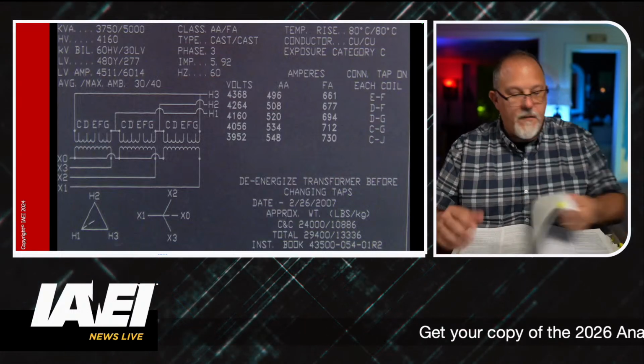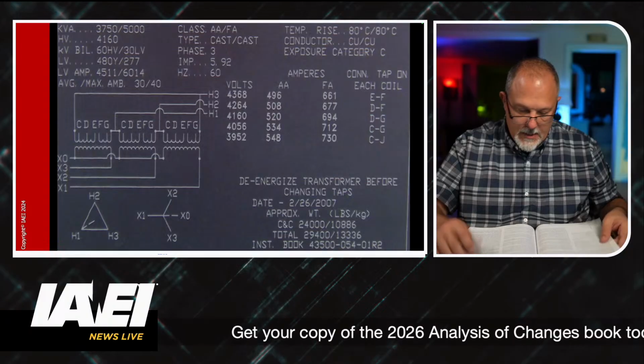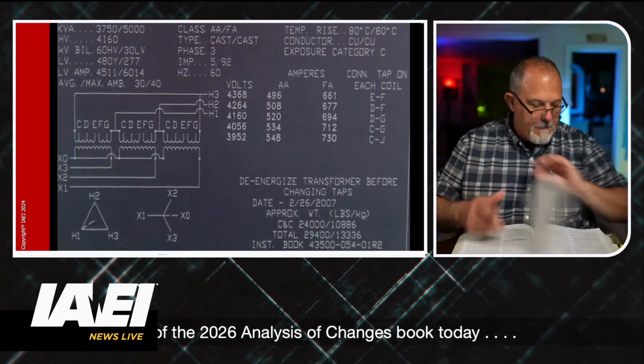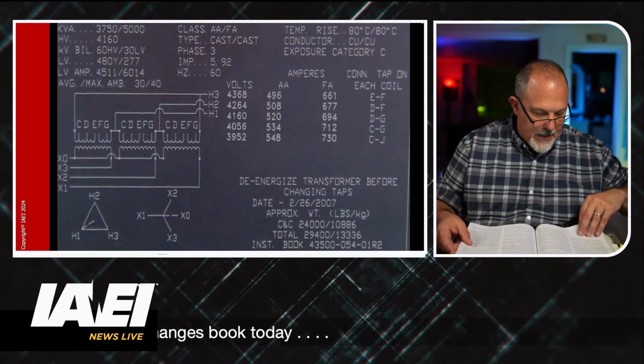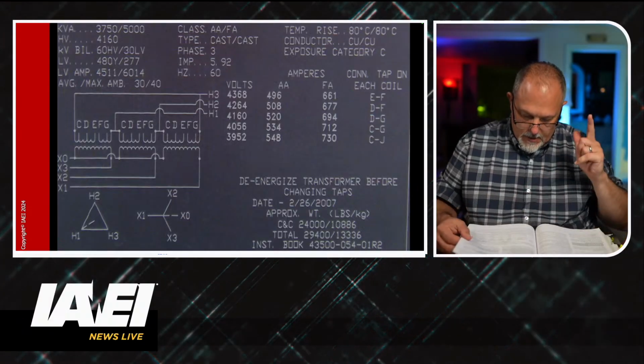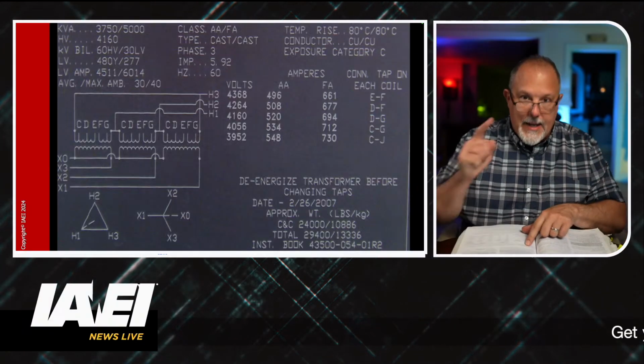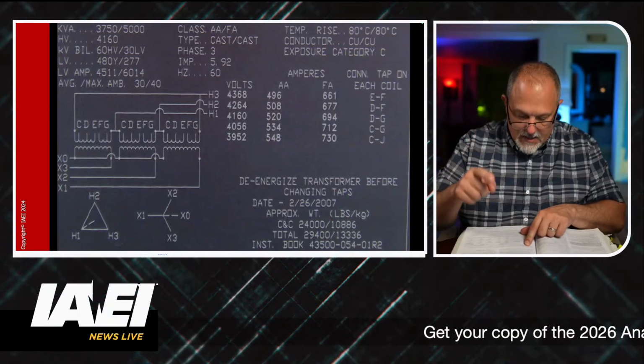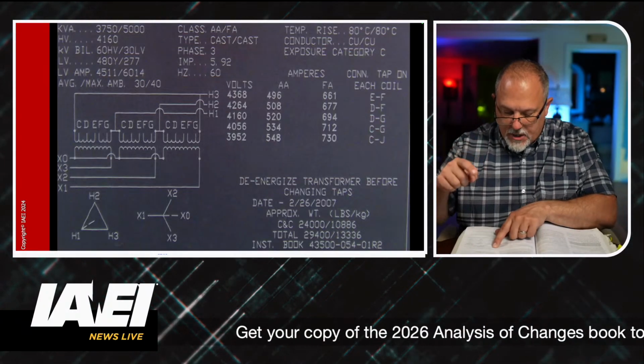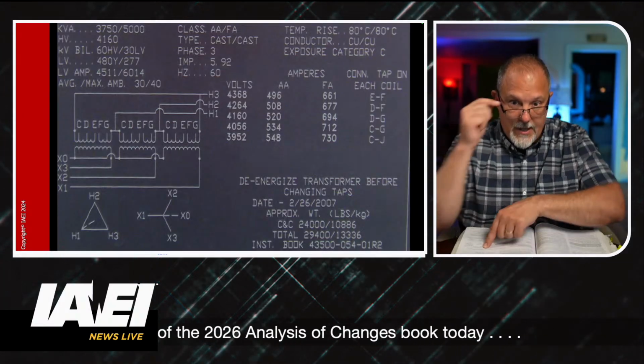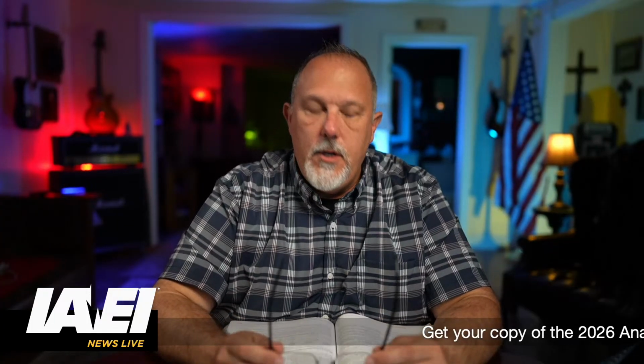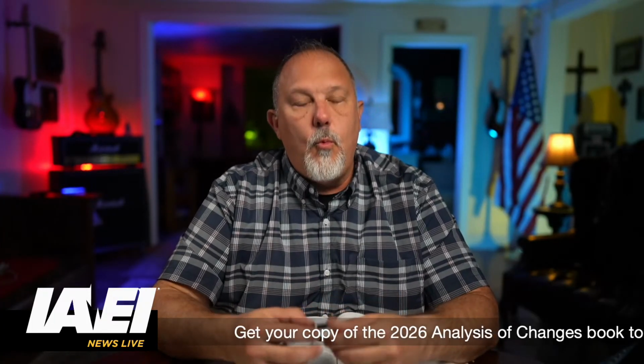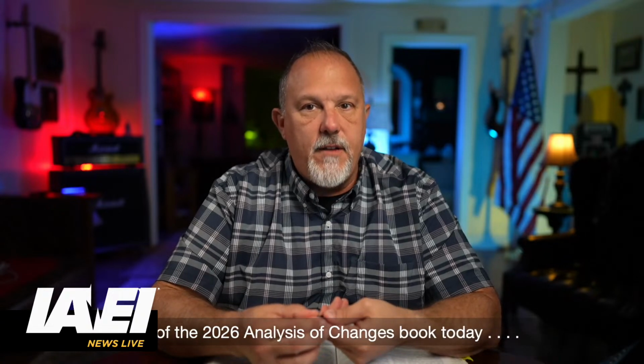If I go to Article 450 on transformers, table 450.3(A) is your maximum rating or setting of overcurrent protection for transformers over 1,000 volts.